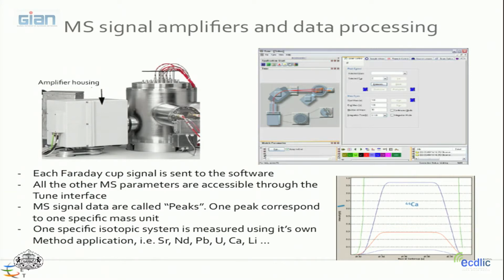But if you want to measure something specific, like very low abundance neodymium in peridotite, then maybe I will change the protocol and we will discuss together to adapt the methodology and the software to your specificity. Or if you want to measure another type of isotopic system, we will discuss together and try to find the best positions for the cups, the best type of filament to use, and what measurement time according to the signal and the noise, etc.